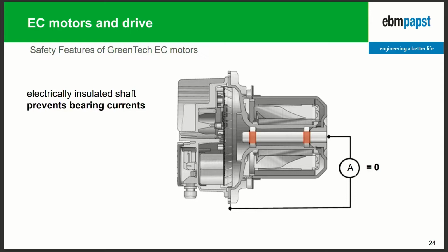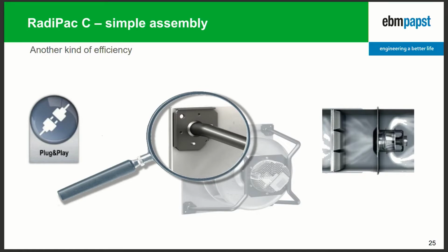And you may have made the experience already when you take a standard AC motor and use a standard VFD, put them together. It may happen that after a few months, the bearings fail. And this has to do with this current through the bearings. We overcome this problem by using an isolated shaft. So the shaft to the bearing is isolated, and therefore no current can flow and no damage of the bearing can occur. So it's also a kind of efficiency when you can take the product out of the box and fix it with a few screws to the unit. So we have created a plug and play, ready to use product, simple use, simple mounting. This can be also seen on our booth.